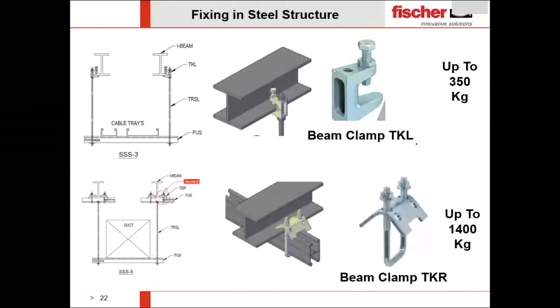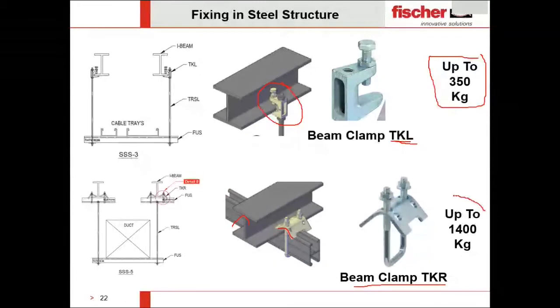The light duty one is called TKL, which can be clamped like a C-shape onto the I-beam, and it can take a maximum load of up to 350 kg per fixing point. The second solution is called TKR, a beam clamp. You have to use a couple of them, one on each side, and you have to use a secondary steel structure like C-channels for support. This can take up to 1400 kg per fixing point.